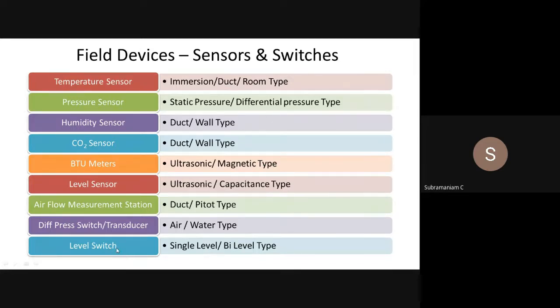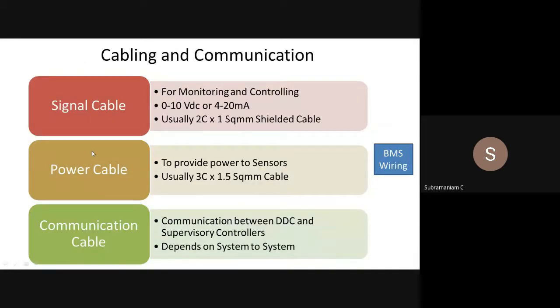So there is a difference between a switch and a sensor. Switch means it will give you only binary. Sensor means it will give you a continuous value. So these are the typical sensors. And for this, we have to use some cabling. So what kind of cabling? One is a signal cable, where we use a twisted and shielded cable, 2 core 1 square mm, which is for this kind of signals and also binary signals.